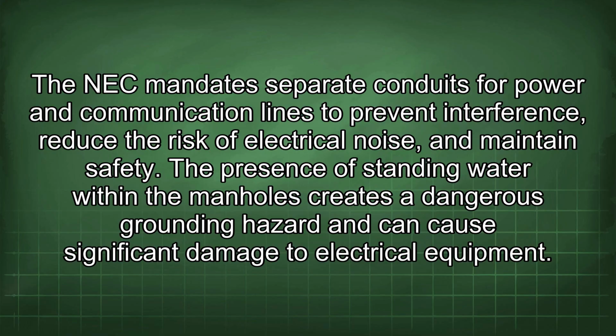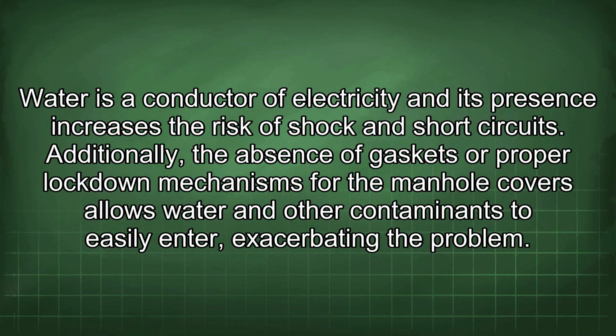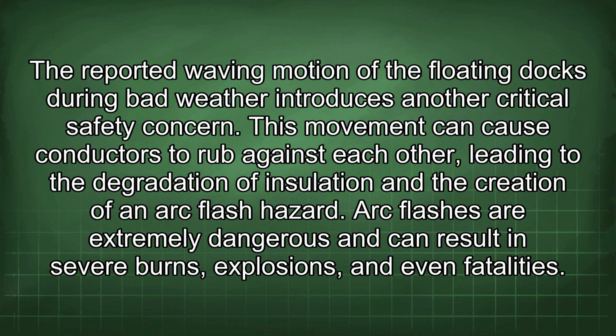maintain safety. The presence of standing water within the manholes creates a dangerous grounding hazard and can cause significant damage to electrical equipment. Water is a conductor of electricity and its presence increases the risk of shock and short circuits. Additionally, the absence of gaskets or proper lockdown mechanisms for the manhole covers allows water and other contaminants to easily enter, exacerbating the problem. The reported waving motion of the floating docks during bad weather introduces another critical safety concern.